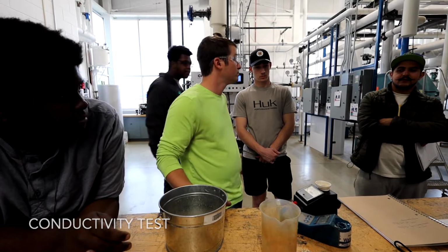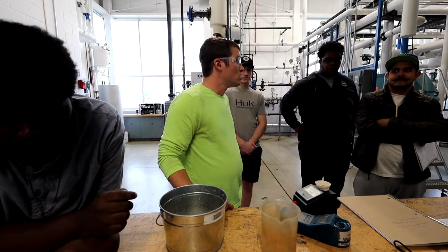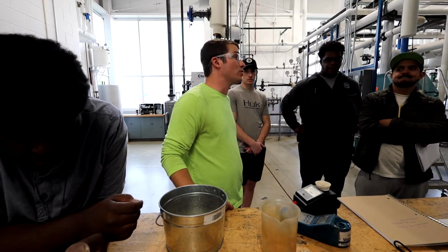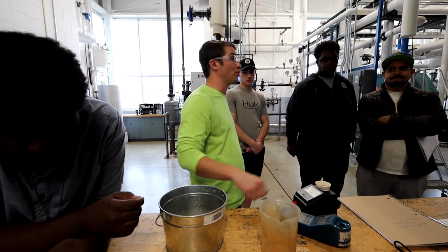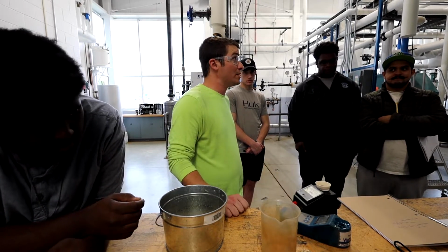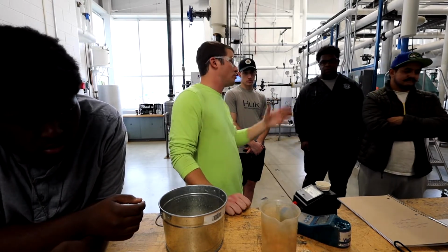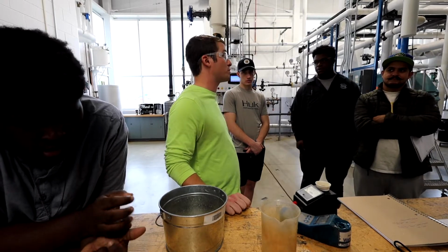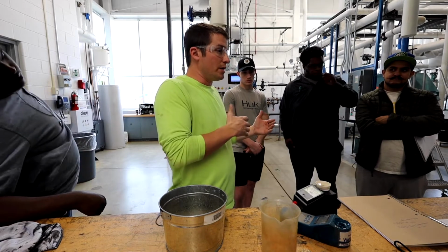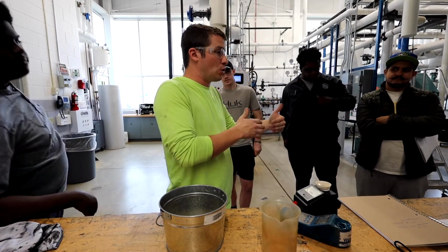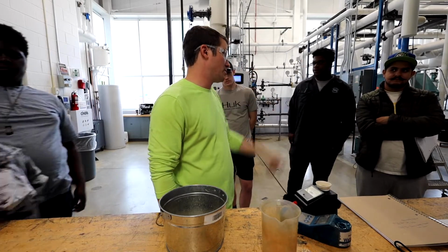What would be the most common numbers to get when you're testing? It depends. It really depends. If you get 99% condensate back, maybe your reading's 30. Or maybe I have customers where it's 300 because they basically get no condensate back, right? Maybe they're doing direct steam injection, so it's 100% fresh makeup and they don't return a lot. It's gonna be higher. If you have RO water, it's going to be lower than if you just have soft, but it all is really gonna be dependent on how much condensate you get back.